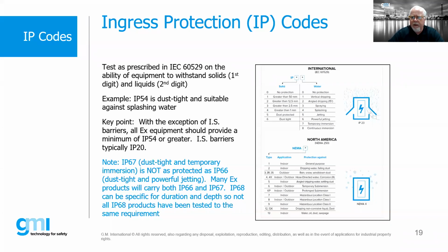In North America, we follow what are called NEMA standards. Now, NEMA standards don't cross directly over to IP codes. They're similar, but they also include, in some cases, description about the type of protection. So, for example, a NEMA 7 enclosure is considered to be an explosion-proof box. So that has nothing really to do with the environmental protection.